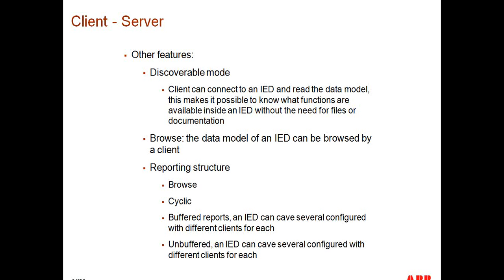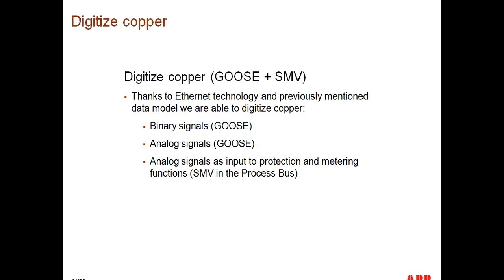Some of the other features that are not contained in either DNP or Modbus, for example, are in Client-Server. It has a discoverable feature where you can have an IEC 61850 based client, and even without knowing what type of device it is, or even without knowing the SEL specific information of that particular device, you can go ahead and discover the data model. You could connect to a relay or a meter and read what information is available from it and make sense of it. You could browse the data model of an IED, and then there's the reporting structure, which supports several triggering mechanisms, such as cyclic. You have buffered reports, you have unbuffered reports, and there's a whole array of flexibility in regards to the reporting structure of IEC 61850 Client-Server.